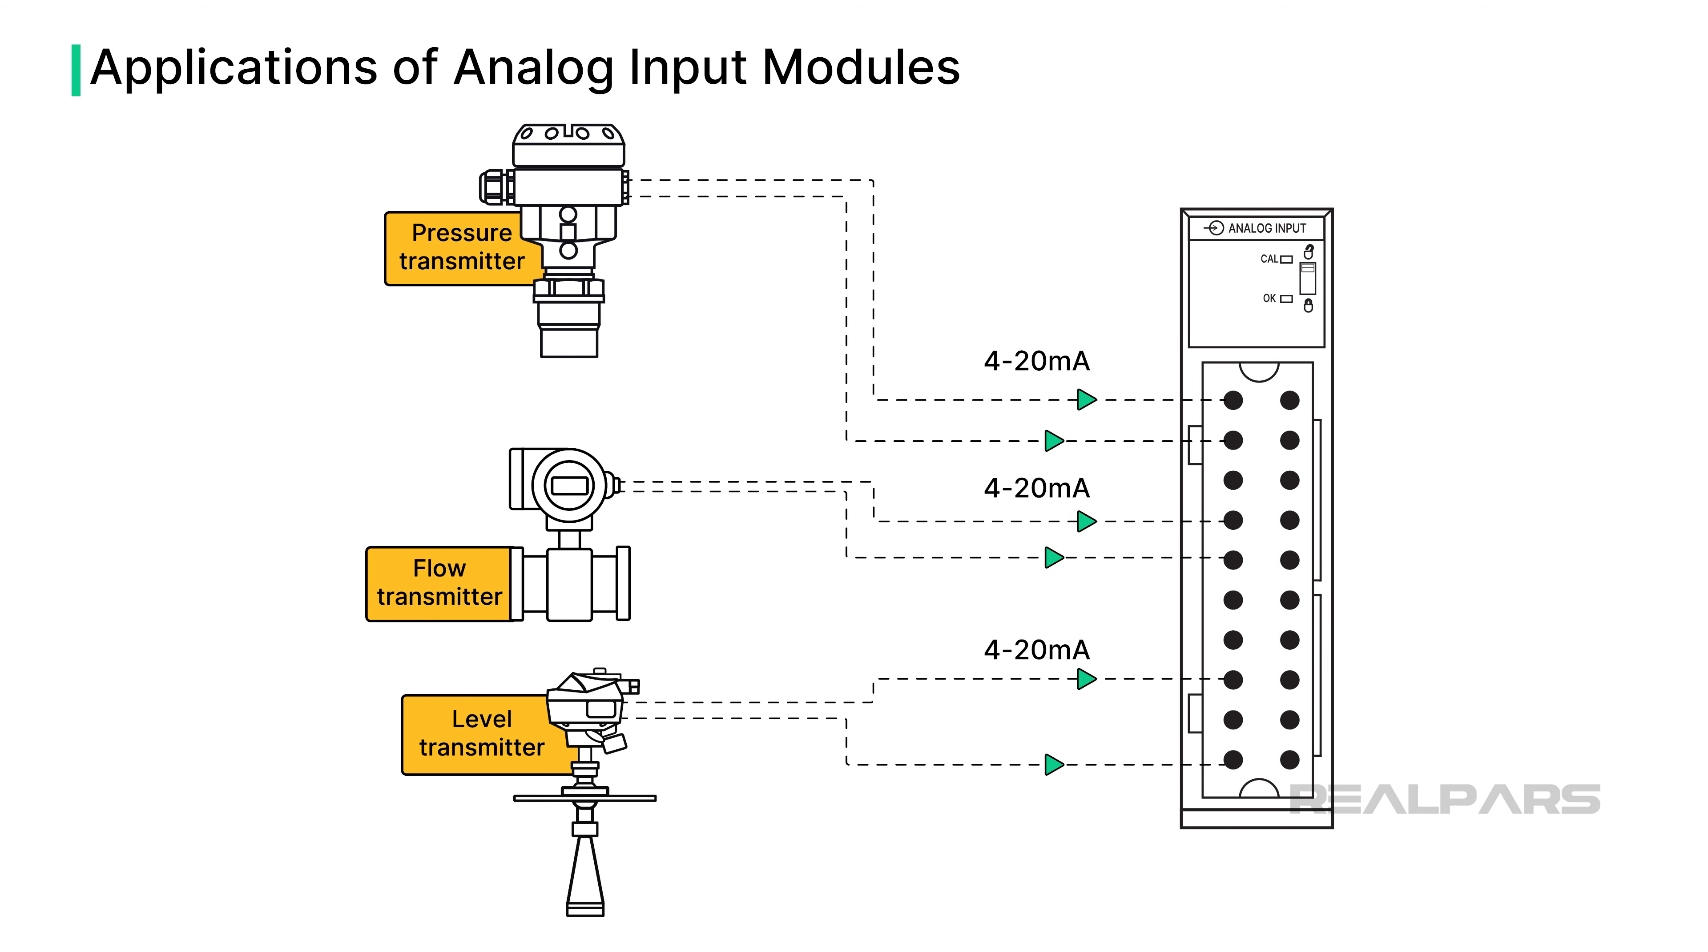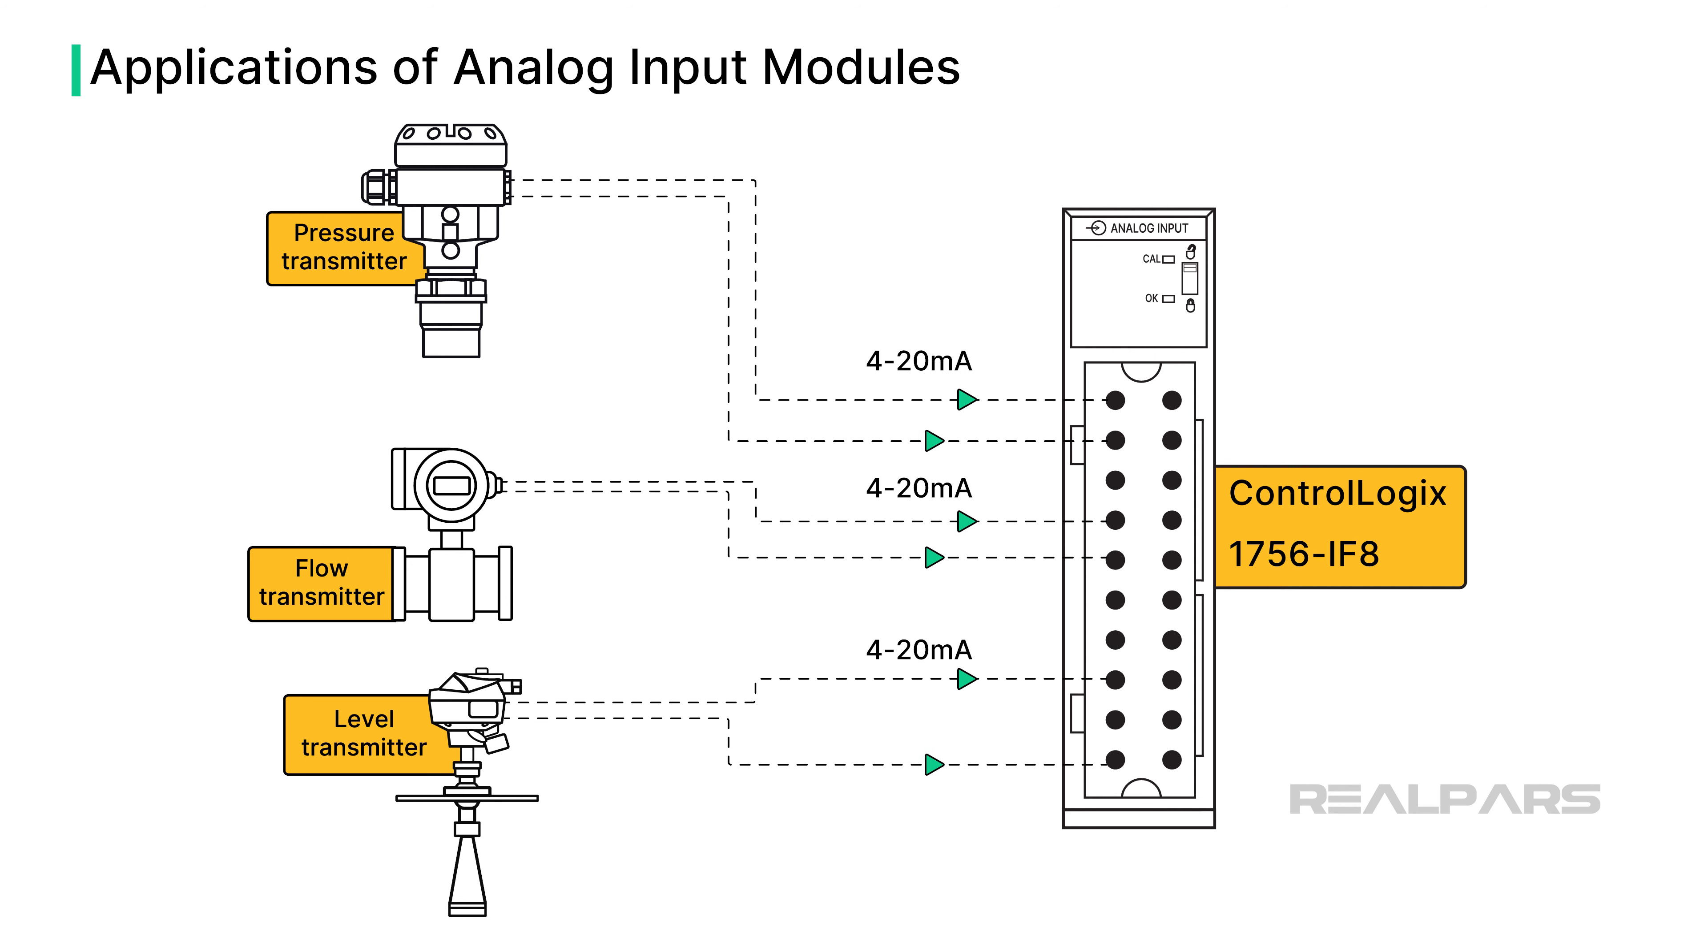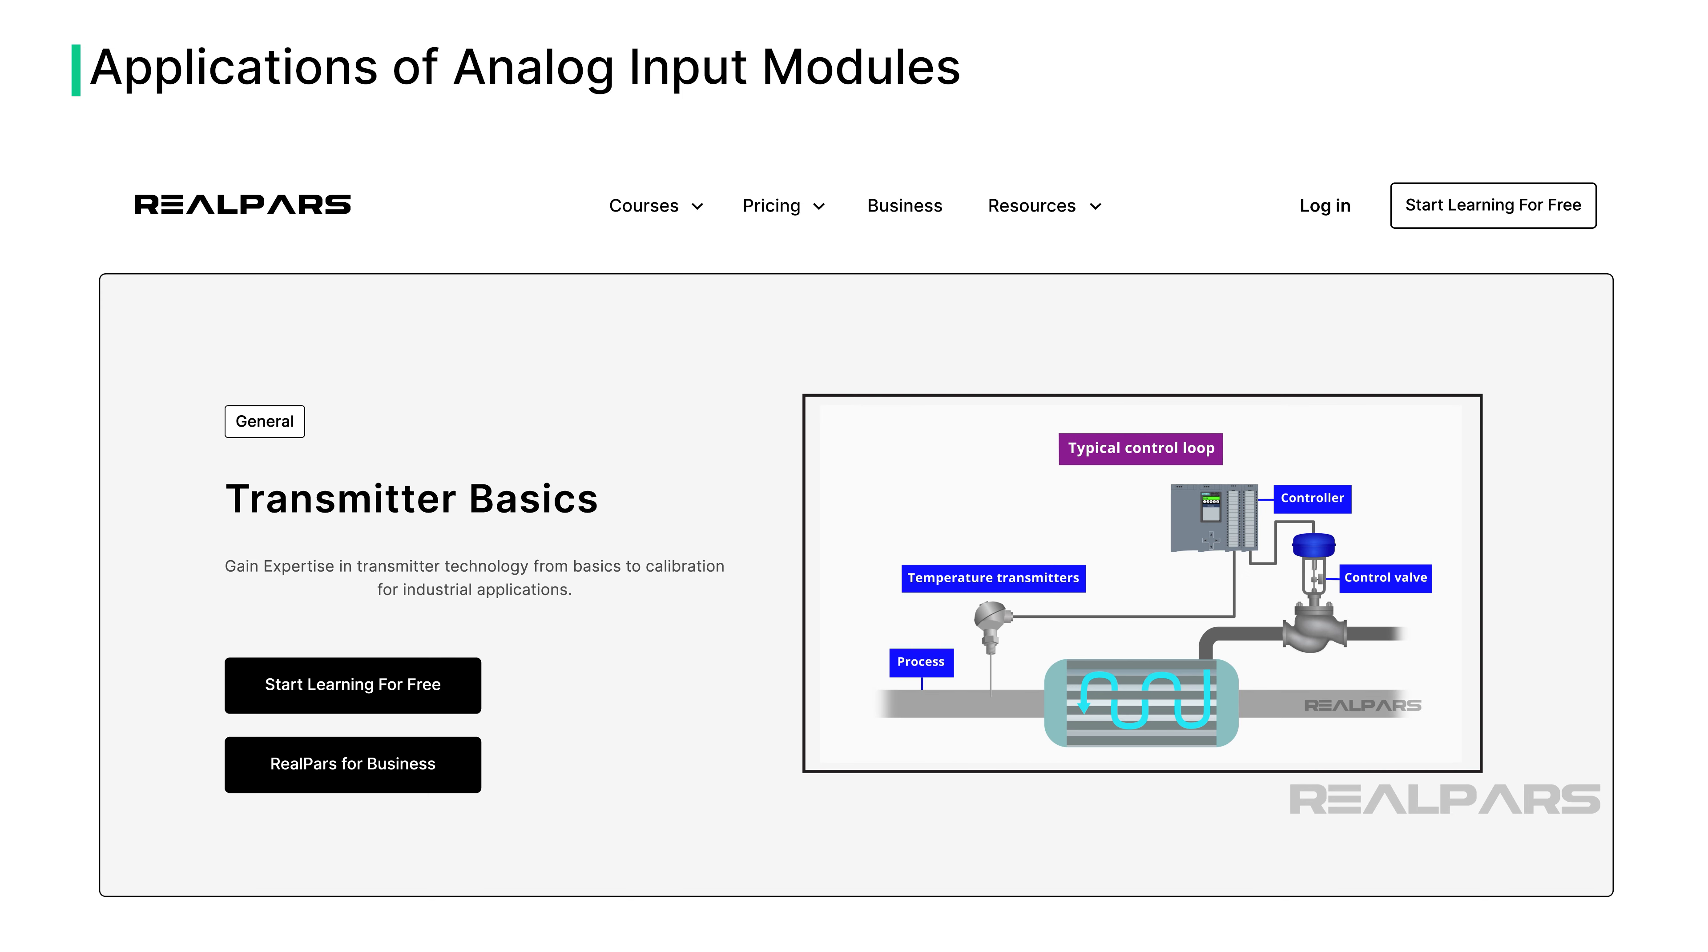We can also use the same analog input module for flow and level measurement. Why? Because the 4 to 20 milliamp signal can represent any variable. For example, the Allen-Bradley ControlLogix 1756 IF8 analog input module can connect up to 8 channels or input loops. Again, if you're a RealPars member, you can learn more about how a temperature transmitter can be calibrated in the Transmitter Basics course.